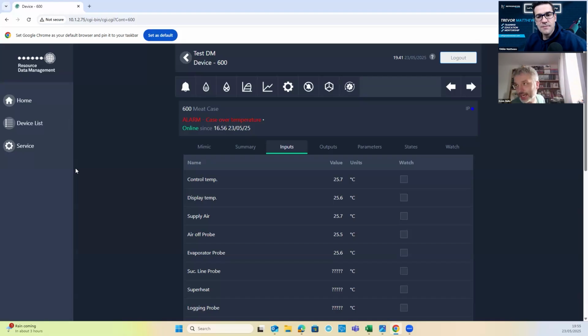I'm also looking at the air on temperature. So I know the air on temperature is going to be warmer than the air off, obviously. If it's way high, let's say -2 Celsius air off and 12 degrees air on, why is it so high? Is something blowing into my fixture? If it's a warehouse type retailer and it's got a big old train unit blowing around, it's going to be blowing in the case. I can pretty much guarantee that because they always are. If you've got cold aisle heating in a supermarket, that can blow into cabinets. We've got a lot more doors coming in on fixtures now. It's a lot rarer to see that, but I'm checking that.